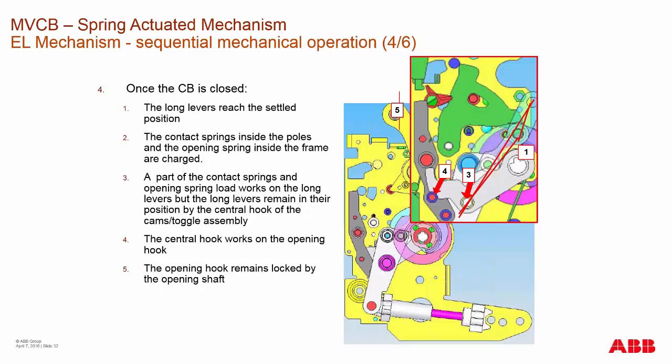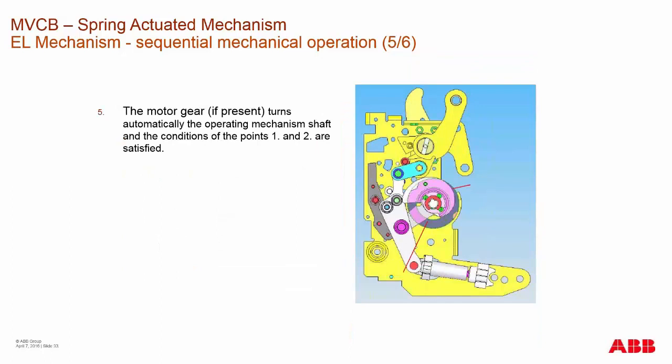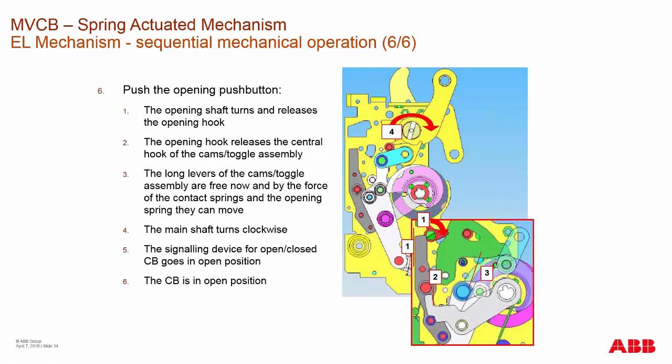Once the breaker is closed and the opening hook is in place, the gear motor starts to turn again through signaling of the main mechanism. When you push the opening button, the opening shaft turns and releases the opening hook, which releases the central hook and the cams toggle, releasing the levers and providing energy to allow the mechanism to open. The main shaft will open on its own due to pressure from the contact force springs under each vacuum interrupter, and there is also an opening spring connected to the main shaft. All energy is translated back from the main housing into the EL mechanism during opening.